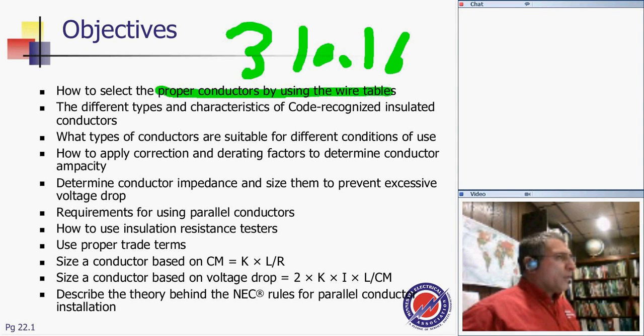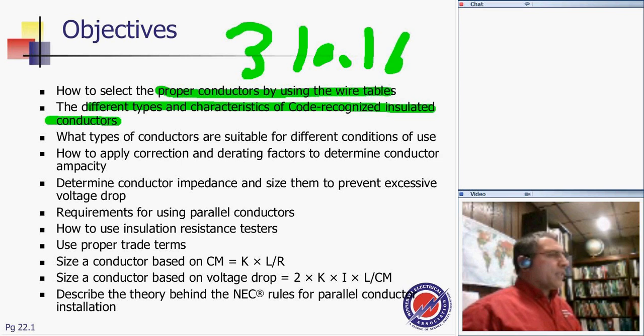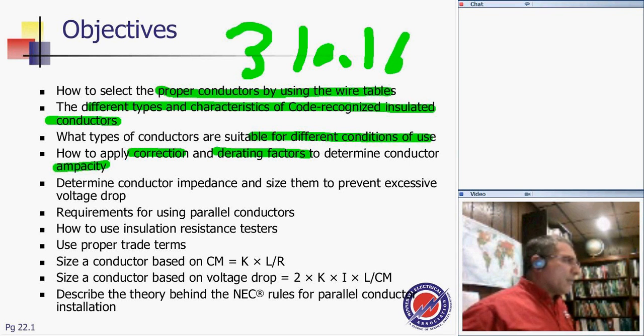Characteristics of code-recognized insulation: what is THHN? What is THW? What is RH? All this stuff. The type of conductor suitable for different conditions of use. That's also the insulation. The correction factors and the rating factors which determine amps are very important things. So I hope, my friends, you can get out of this class tonight knowing how to properly use 310.16 with the ratings, and how to identify and understand the insulation: THHN, THW, and so forth.